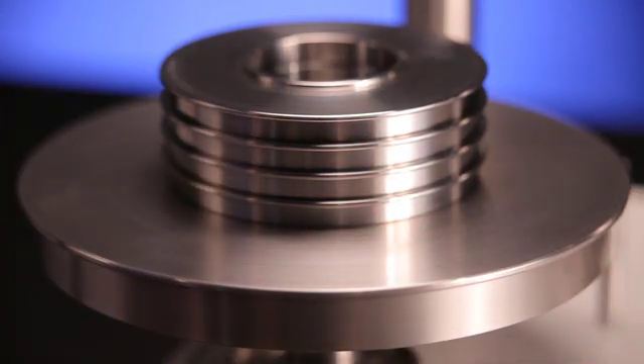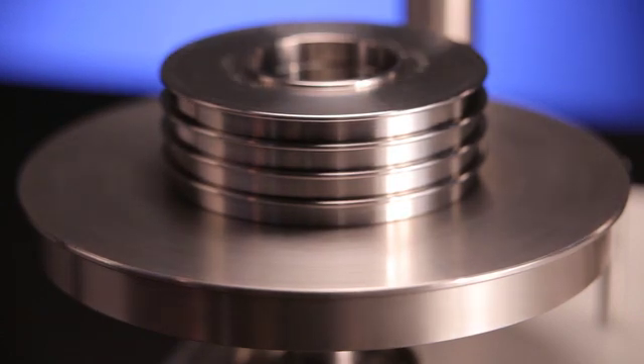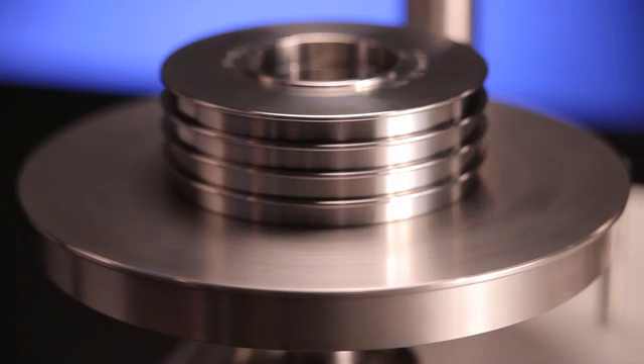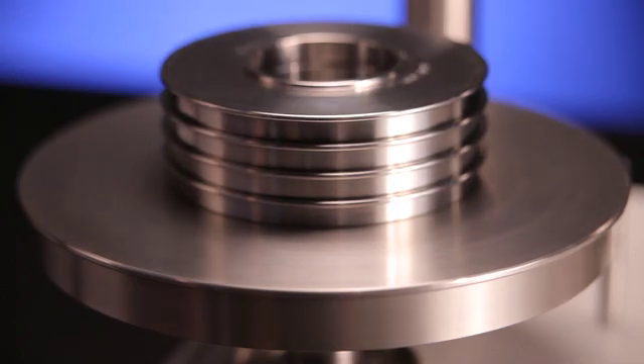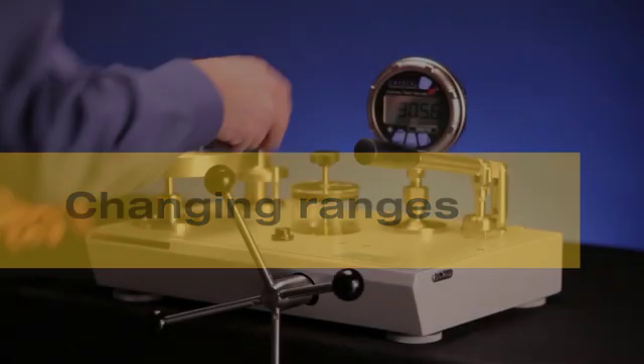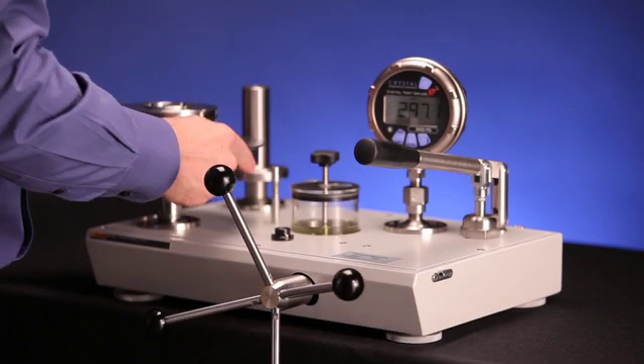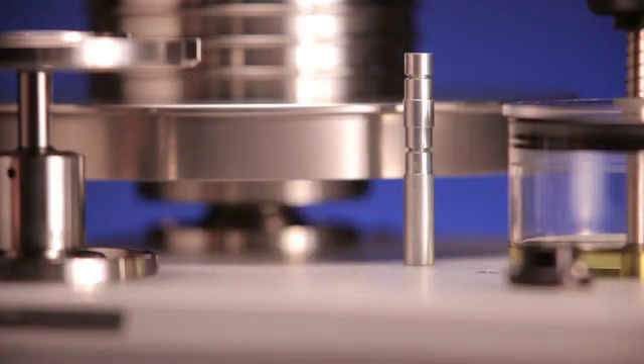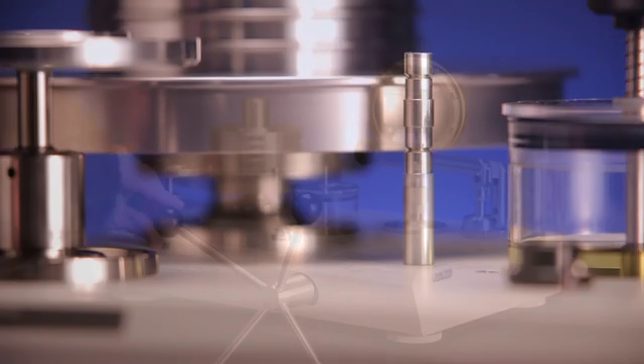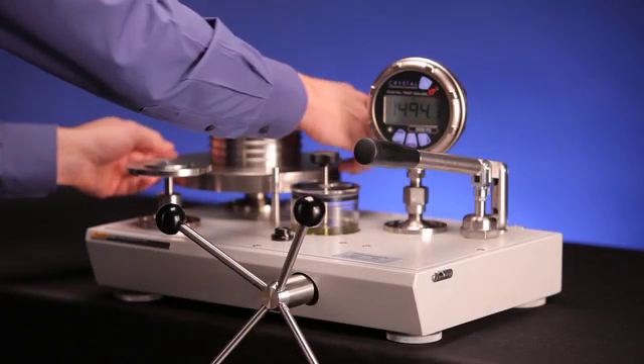Do not rotate the weights when they are at the top or bottom of travel. If the weights are difficult to rotate or they stopped abruptly, then the piston and cylinder may require cleaning. No valves need to be changed to select the piston. The unused piston will simply move to the top of travel and seal.